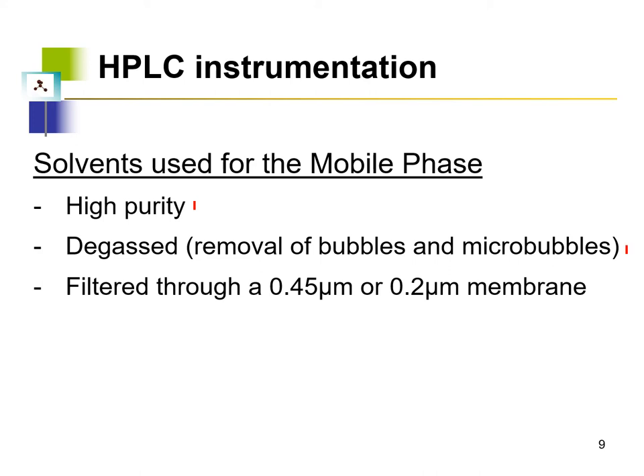The second criterion is that solvents must be degassed — bubbles and micro-bubbles of air must be removed prior to use. Most modern instruments have in-built degassing units that automatically degas HPLC-grade solvents as they run through the system. Additionally, samples should be filtered with approximately a 0.5 micrometer filter to ensure no small particles are present that could damage the column or cause high pressure buildup.